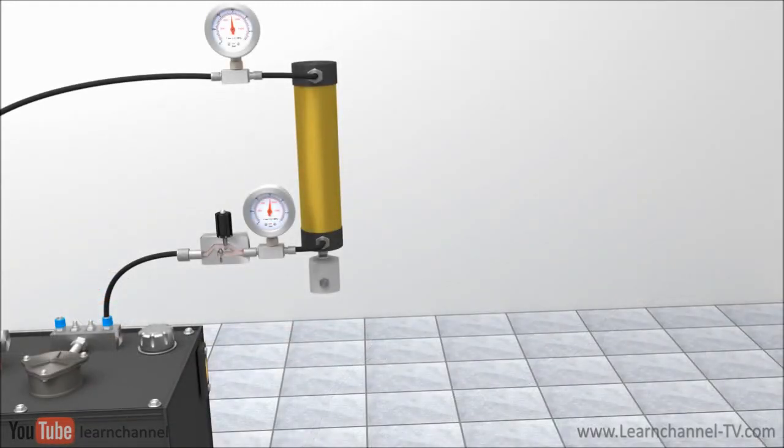To overcome this risk, we place the flow control valve at the outlet of the cylinder. We call this method meter out. Now pressure is built up at the outlet side of the cylinder and even negative load can hold.